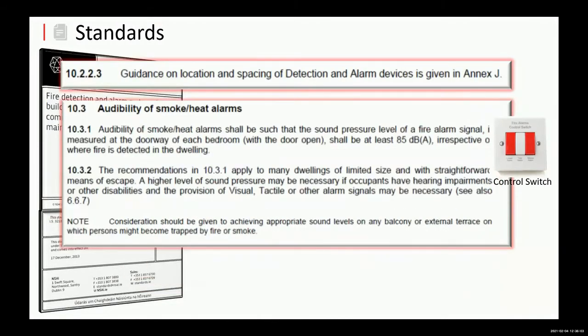So audibility of smoke and heat alarms. The audibility, I suppose, it's 85 dB at 3 meters is what we have to manufacture the units at. In the old way of doing it, before we started putting smoke detectors in the bedrooms, we had to get 85 dB at the bedroom door, and it had to be within 3 meters of any bedroom door with the door open. But now the fact that we're putting in units within the bedrooms themselves, we're definitely getting 75 dB at the bed head. So it's still there in the standards, but it's a non-event really.